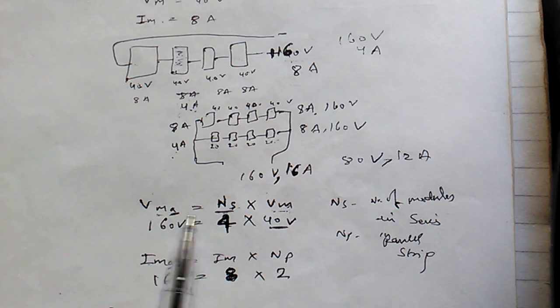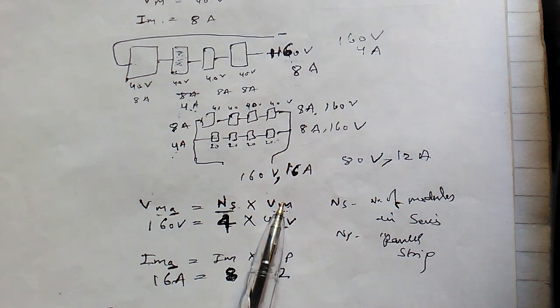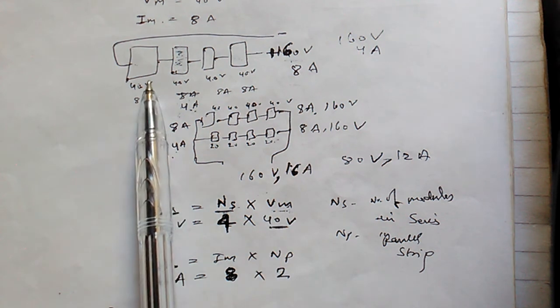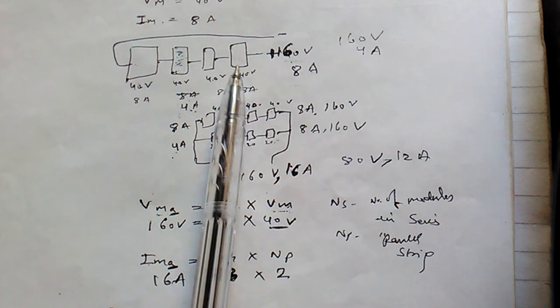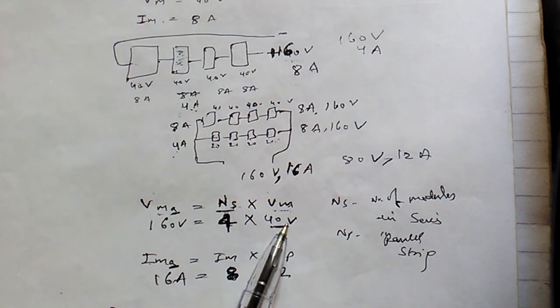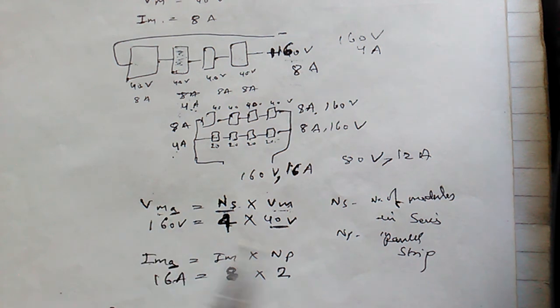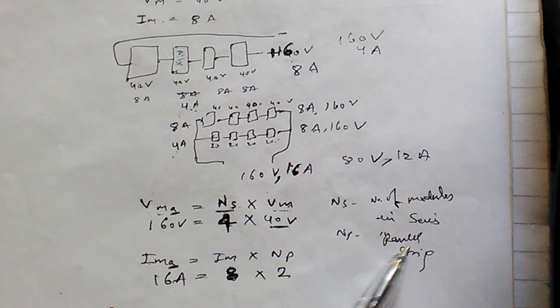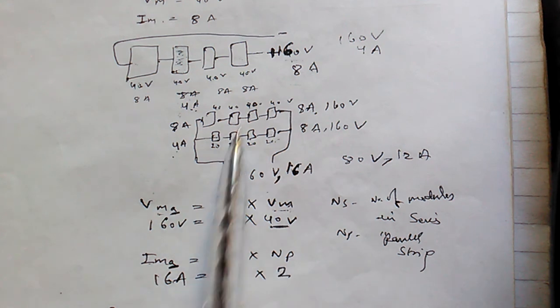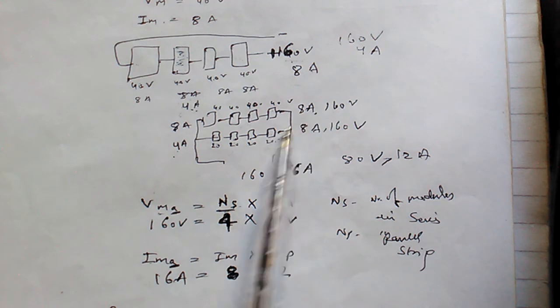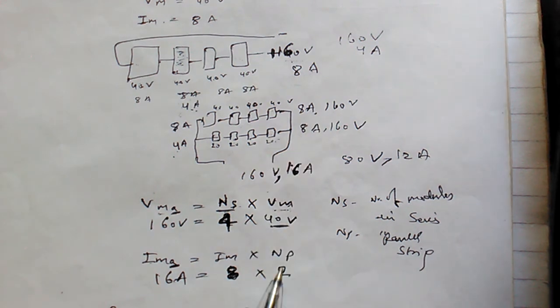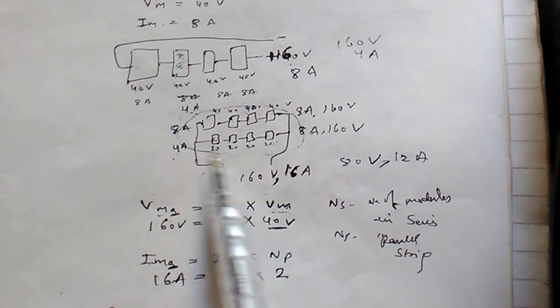The array voltage formula is: Vma = Vm × Ns, where Vm is the single module voltage and Ns is the number of modules in series. For example, 40 volts × 4 modules = 160 volts. The array current formula is: Ima = Im × Np, where Np is the number of parallel strings. For 8 ampere × 2 strings = 16 ampere total array current.